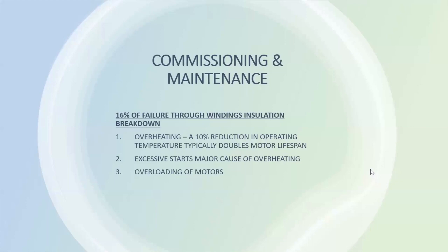Now let's look at the 16% of the failures which are caused by the motor winding. Whenever a motor is overheated, there is a reduction in lifespan. Whenever a motor operates at 10% below its temperature, you double its lifespan. So the lower the temperature, the longer the lifespan of the motor. So we must ensure that our cooling system, the fan cover which guides air to cool the motor through the cooling fans, is working effectively, because the cooler the motor, the longer the lifespan of the motor.